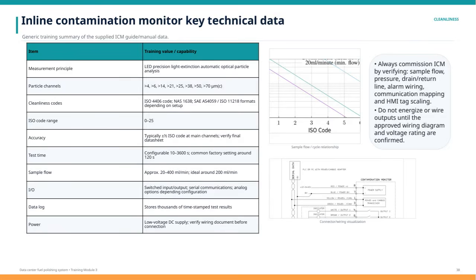Here we have the key technical data for the Inline Contamination Monitor, or ICM. This device uses a highly precise LED light extinction method to automatically analyze particles in a fluid. It can detect particles across multiple size channels, ranging from greater than 4 micrometers up to over 70 micrometers, which helps ensure detailed cleanliness assessment. The cleanliness results are reported using widely recognized standards like ISO 4406, NAS 1638, and SAE 4059, depending on the setup. The ISO cleanliness codes can range from 0 to 25, with the device typically achieving an accuracy of plus or minus half an ISO code at the main particle channels. This gives us confidence in the reliability of the data it produces.